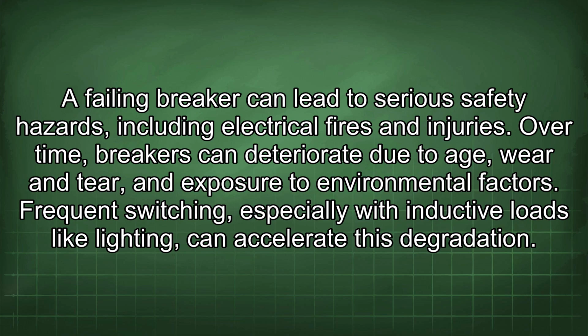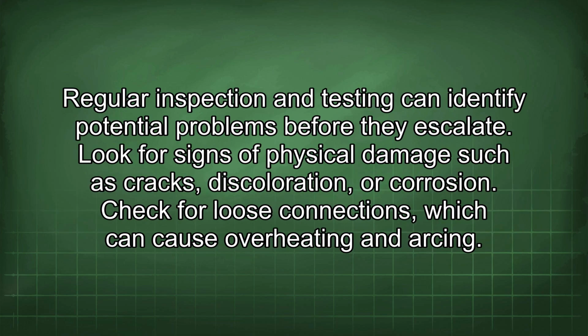Over time, breakers can deteriorate due to age, wear and tear, and exposure to environmental factors. Frequent switching, especially with inductive loads like lighting, can accelerate this degradation. Regular inspection and testing can identify potential problems before they escalate. Look for signs of physical damage such as cracks, discoloration, or corrosion. Check for loose connections, which can cause overheating and arcing.